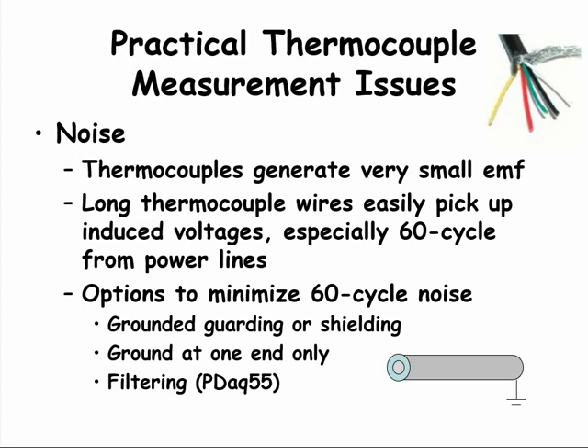Small temperature changes will produce small EMF changes, so it is hard to find a small EMF if there is a lot of noise. Another major source of error comes from induced voltages from power lines and other electronic equipment near where the thermocouple wire goes. Induced voltage in thermocouple and other sensor lines is not desirable. There are some short thermocouples just a few inches long. In some applications, thermocouple wires can run thousands of feet. Two options for managing induced voltage include using guarding or shielding.